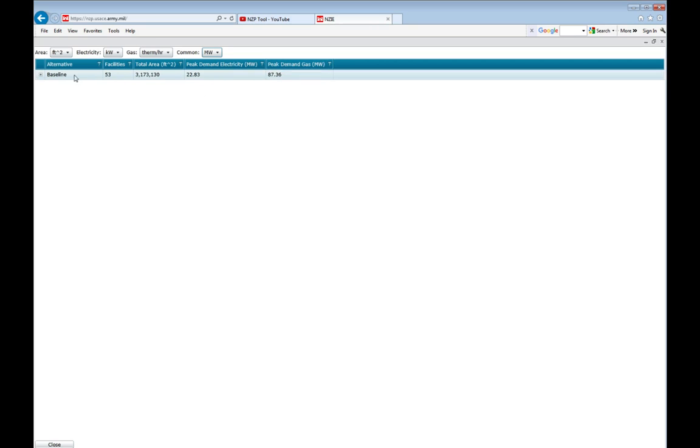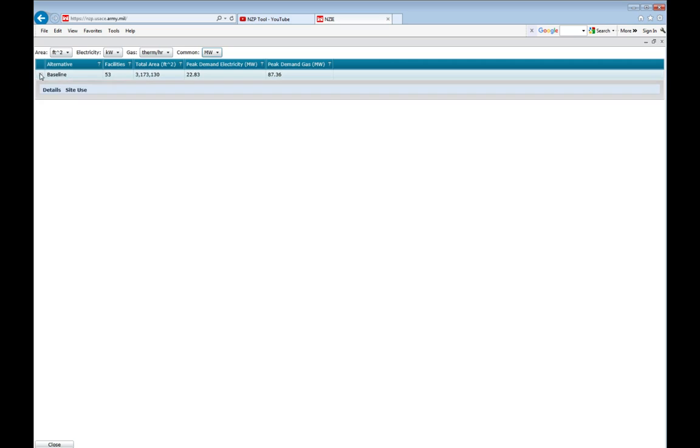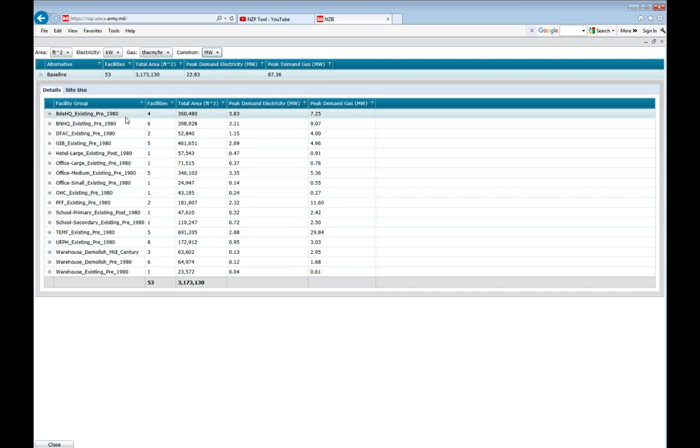And then I like to see what the contributions are to that peak demand. Like I said, it's 3.2 million square feet, so it's kind of large, and it's a fairly large demand. So this is how you check how big a service you need. And like I said, we've got breakdowns here. Once again, it breaks down by building type.